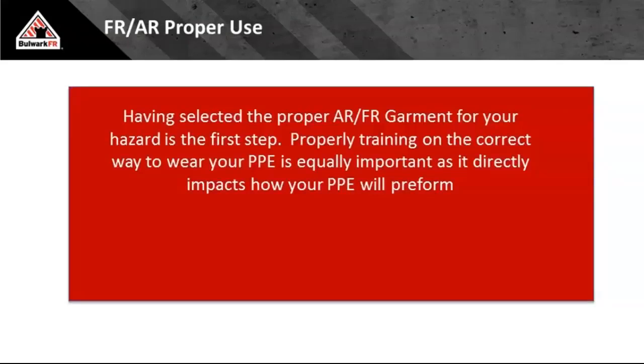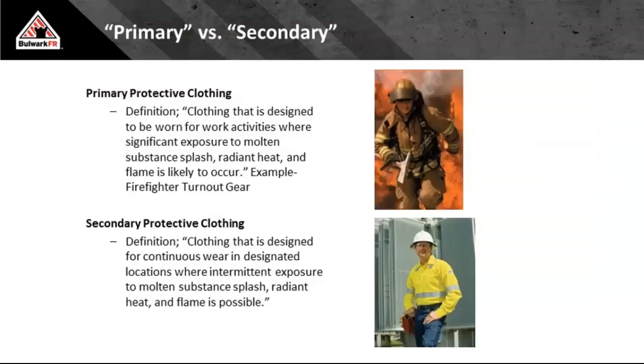So now you've selected your PPE for your hazard. You've gone through, you've done your hazard risk assessment, you've done your arc flash hazard analysis, you know what your incident energies are, you've chosen whether you're going to follow the incident energy method or the Cat method, and now you're moving on to proper use. Think about it this way. When we look at utilizing arc-rated clothing, it is actually considered secondary protective clothing. So if you have secondary, that means you must have primary. So what is the difference between secondary and primary?